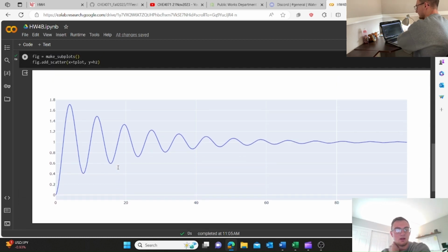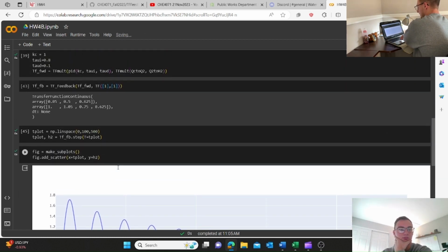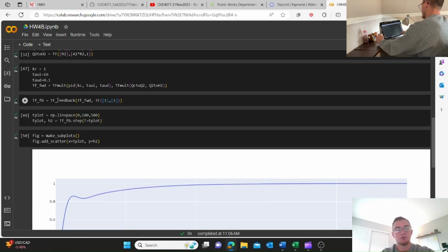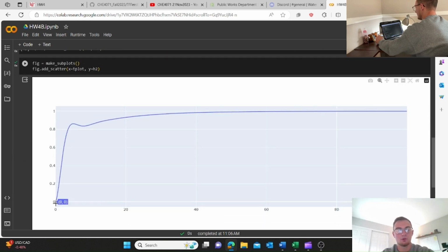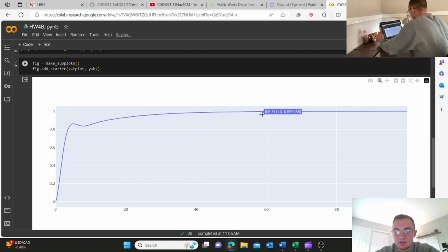And you see here, when I was practicing this before, I had already changed our integral control here to 0.8. But what we originally had it at was 10. And what we can see when we run this is that when we do our step change and we have our integral control at 10 here, we go from our initial steady state in our process, and we go up some, and then after some time, looks like around 50 or 60, we start getting to our full 1 step change that we had requested of the system.